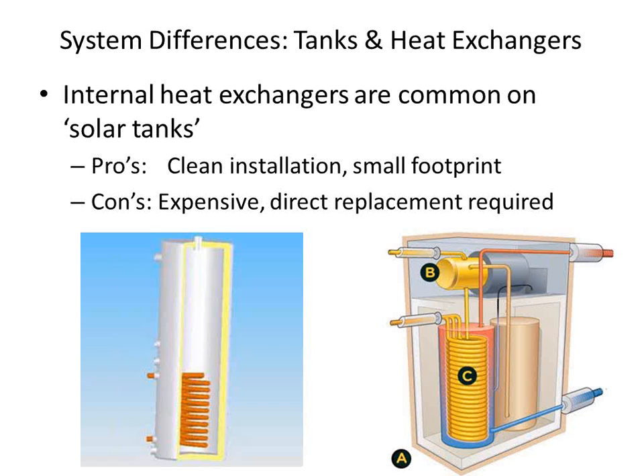Some manufacturers use external heat exchangers. Basically what you're going to have is copper coils inside a small sleeve of domestic hot water. You heat up that small sleeve, and then thermal cycling or a circulator pump is going to move that water from the heat exchanger up to the top of your storage tank. That will displace water in the storage tank, and it will drive more cold water into the heat exchanger.